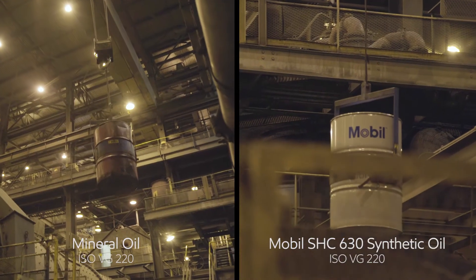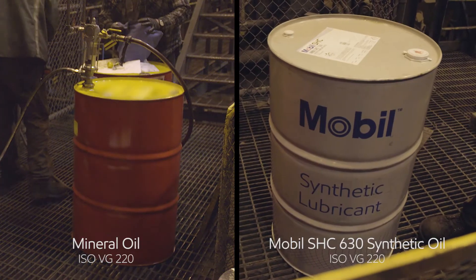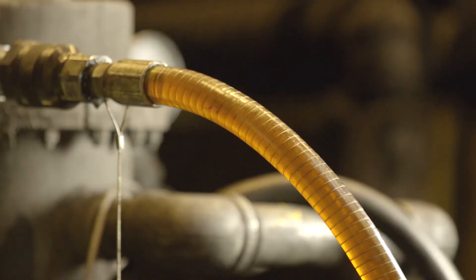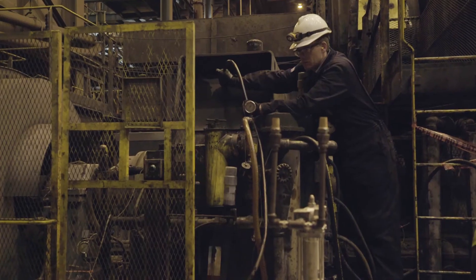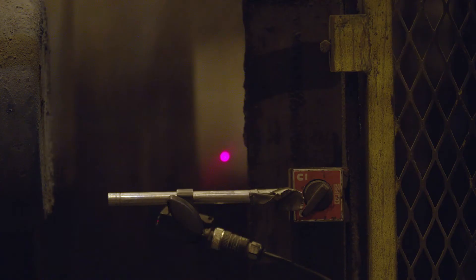The two lubricants we're testing are a competitive mineral EP gear oil ISO VG 220 against the Mobil SHC 630, which is a synthetic ISO VG gear and bearing oil. A field demonstration like this would normally take one to two months, but we've been able to streamline that through the Mobil Serv offer down to one to two days.